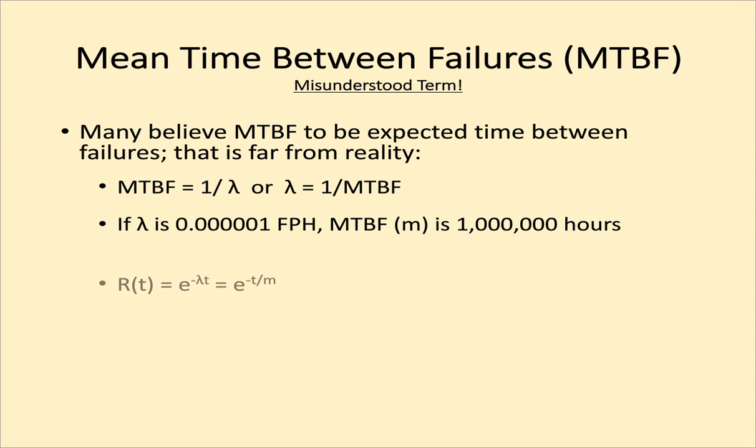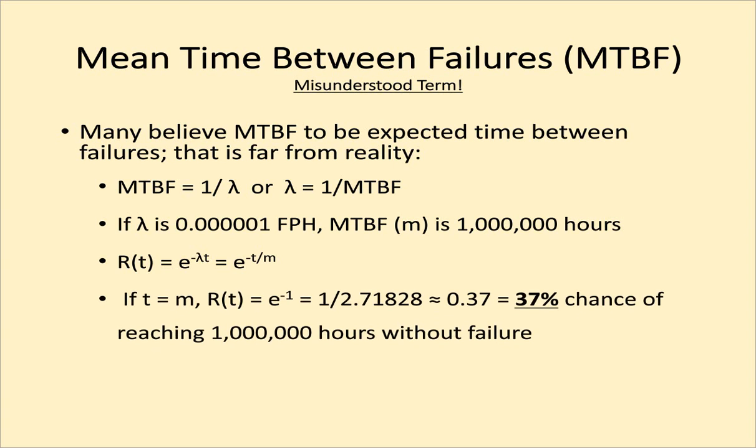Then if we plug that into the reliability formula, which is R = e^(-lambda t), and substitute in the reciprocal of lambda, which is MTBF, and perform the calculations, we end up with e^(-1), which is 1 over 2.71828, or 0.37.